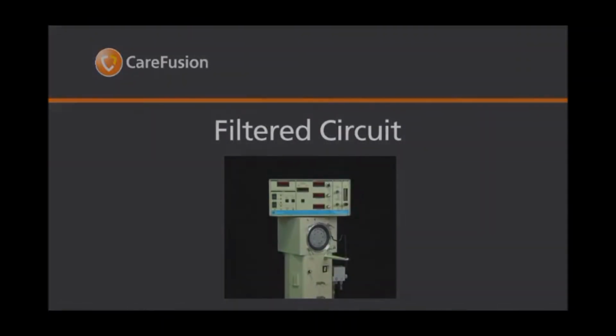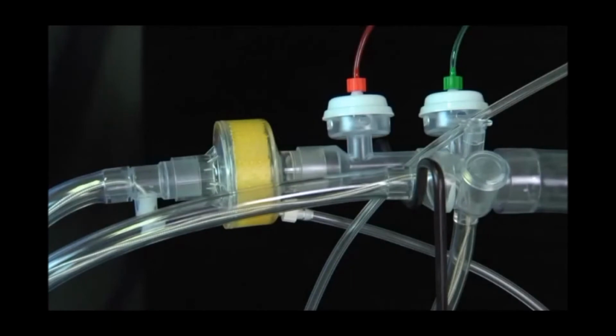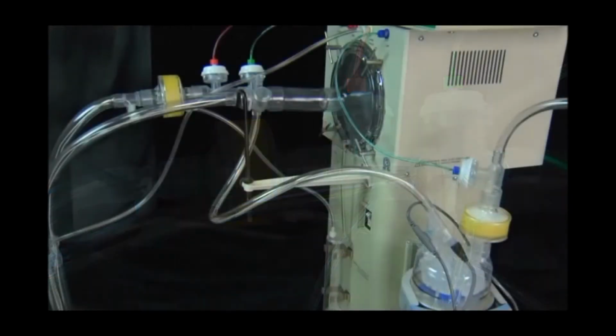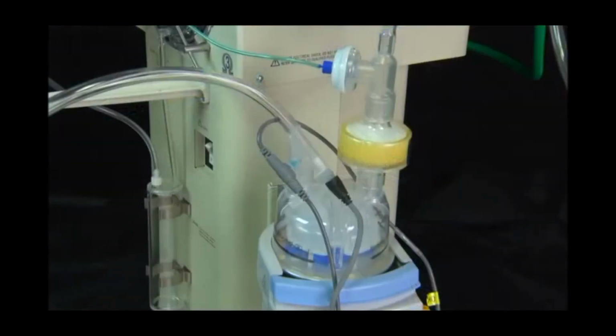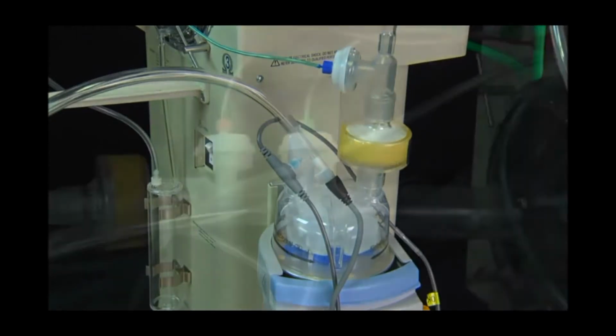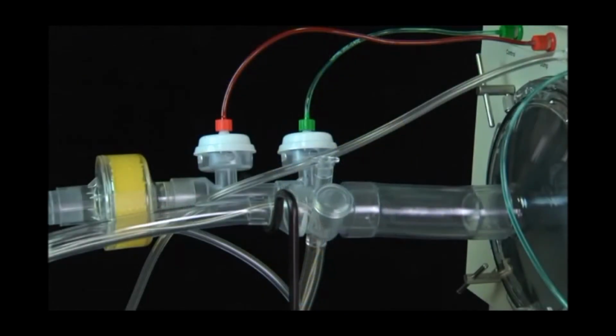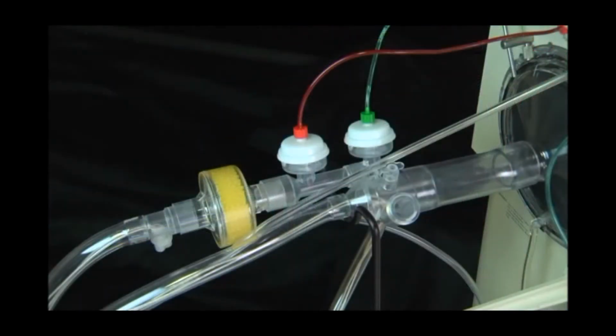The filtered circuit. The filtered circuit for the 3100 provides filtration of gas from the inspiratory and expiratory limb using a HEPA filter. The setup of the 3100 circuit is essentially the same as the non-filtered circuit. The limit valve is placed on the dry side of the humidifier chamber. This ensures the filter stays dry so it does not have to be changed. The dump valve has been moved next to the control valve behind the expiratory filter. Special connecting tubing for filtered circuits is provided to account for these new valve positions.